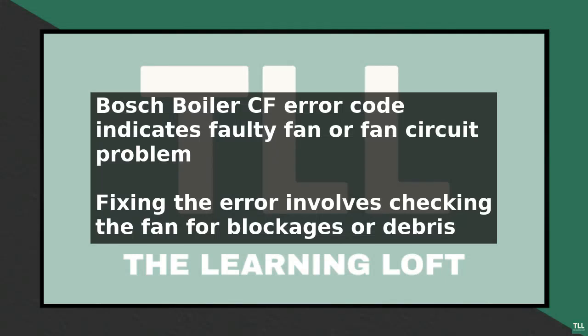How to fix Bosch Boiler CF error code is a comprehensive guide to understanding and resolving the common issue in Bosch boilers. The CF error code indicates a faulty fan or a problem with the fan circuit. To fix the error, start by checking the fan for any blockages or debris. Ensure the fan is clean and free from dust, as this can prevent it from working correctly.